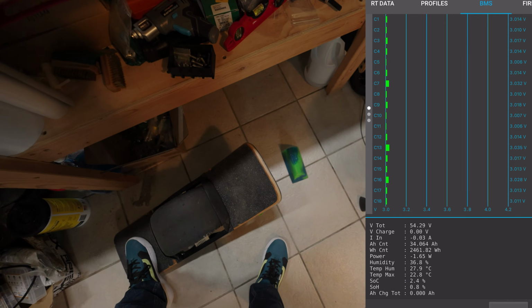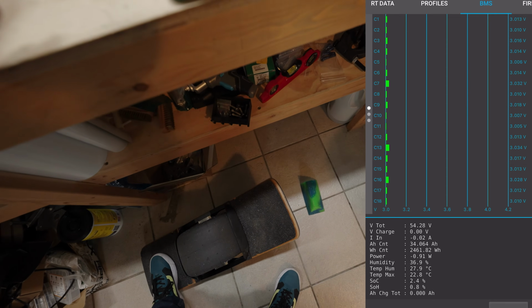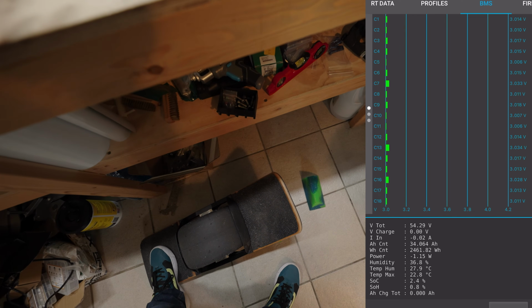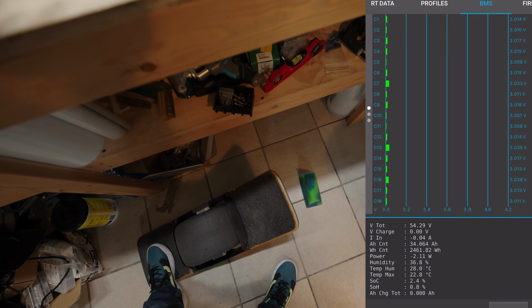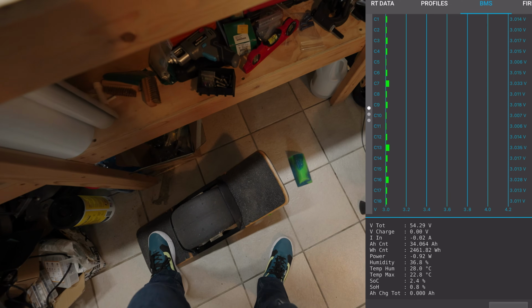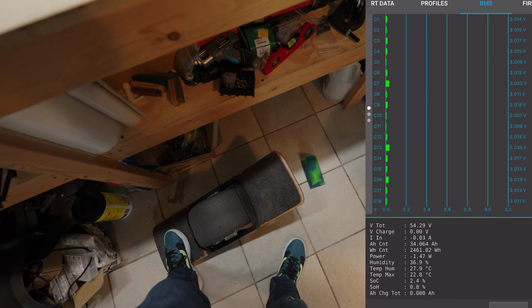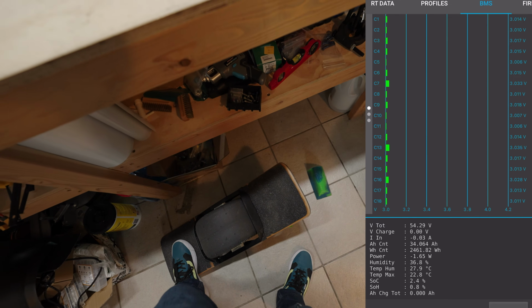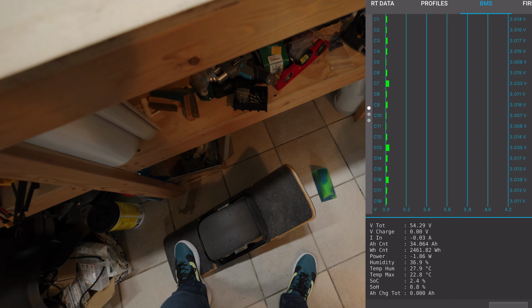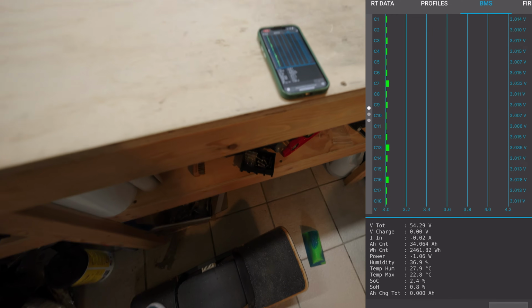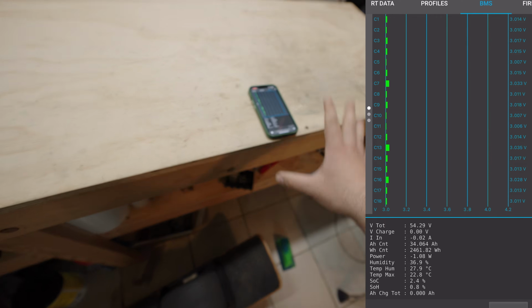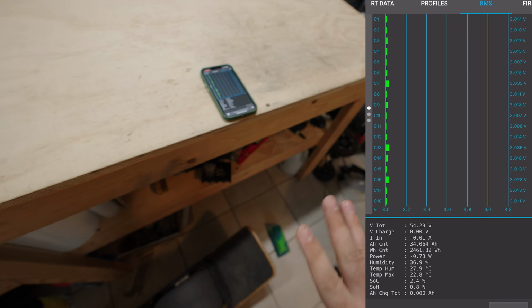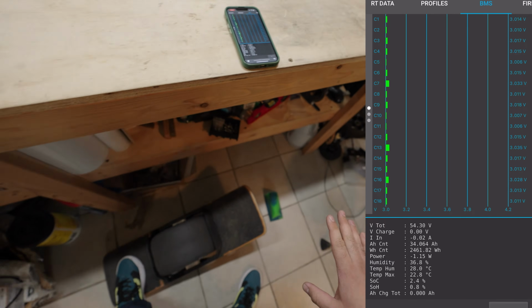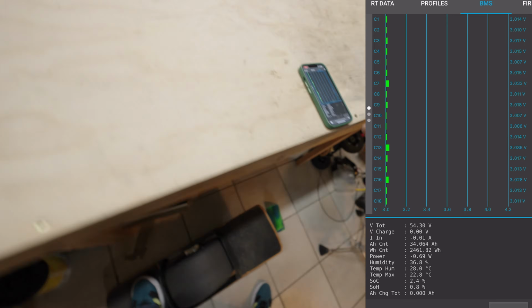That's going to pull the cells down below 3 volts. Some will hit 2.5, some might go below that, and that wouldn't necessarily be a bad voltage range in the moment, because you're seeing a dynamic load voltage, not an at-rest voltage. Then you'll see the cells settle.